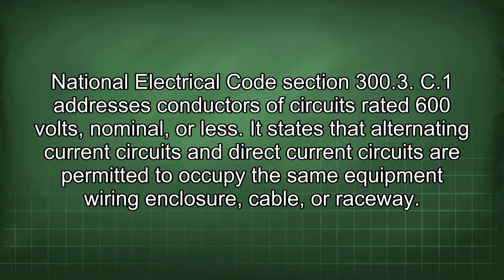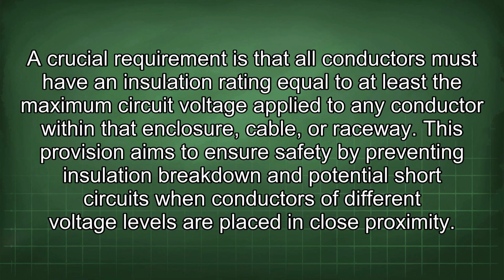National Electrical Code Section 300.3(C)(1) addresses conductors of circuits rated 600 volts, nominal or less. It states that alternating current circuits and direct current circuits are permitted to occupy the same equipment wiring enclosure, cable, or raceway. A crucial requirement is that all conductors must have an insulation rating equal to at least the maximum circuit voltage applied to any conductor within that enclosure, cable, or raceway.